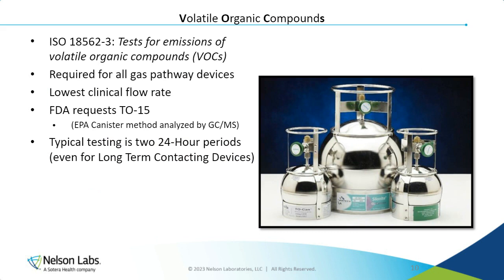Moving on to volatile organic compounds, this test is required for all gas pathway devices. Here, the devices are tested in a similar fashion. Clean, dry air, or dry nitrogen may be pushed through the device. If the air is tested just through the device, it's only testing the interior of the device.